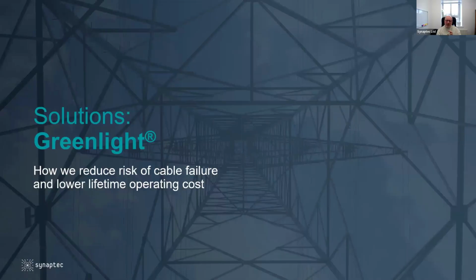The other part of this is, well, that's after the fact. Is there a way to manage cable systems? They could be underground, they could be underwater. Is there a managed way to monitor them and catch an early warning sign of problems so that you're notified in advance of the fault that something's going to go wrong? Because if you get enough time to respond, you can plan an intervention and avoid the failure, which would be even better, right? And that is something we also do, and the product solution is called Greenlight.